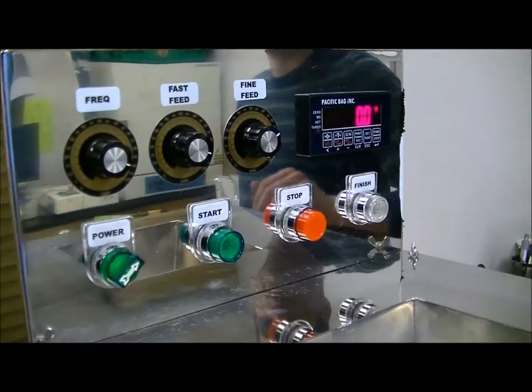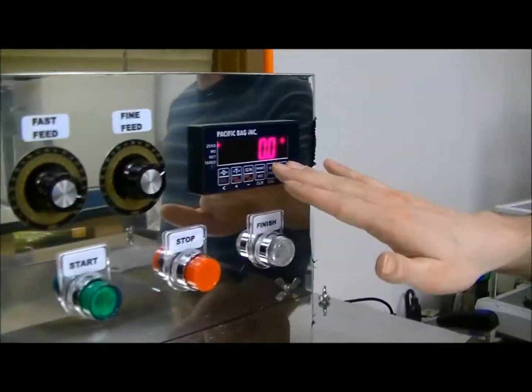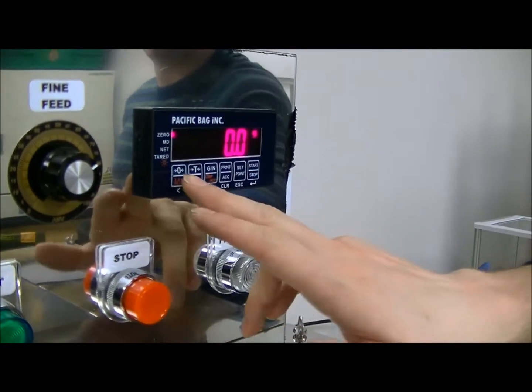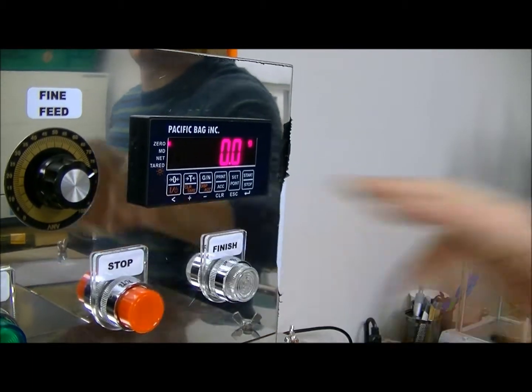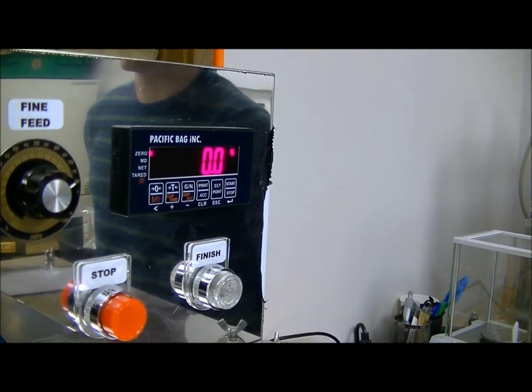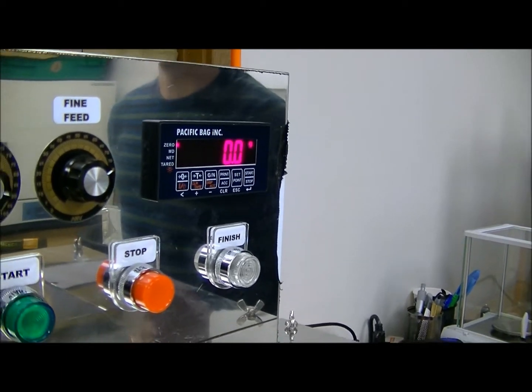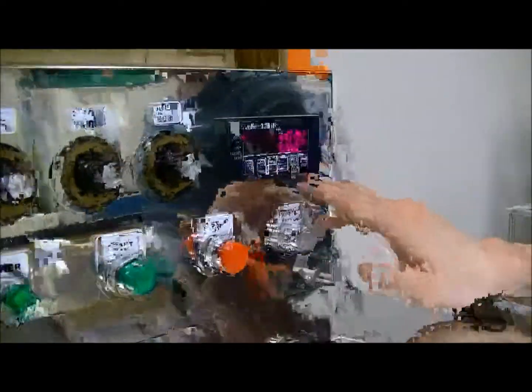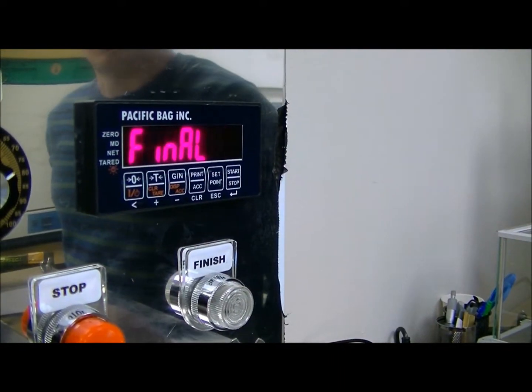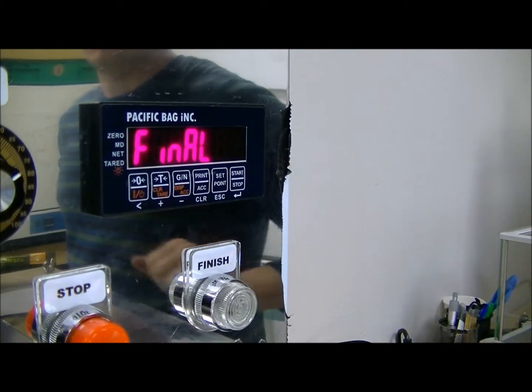The first thing to do is, if the load cell has not been zeroed out, press the button on the left here to zero it. In this case it was already zeroed, so you didn't see any change. If you want to change the set point of the weight, you're going to push the button second in from the right here that says set point. At that point you'll see the weight setting for the final.